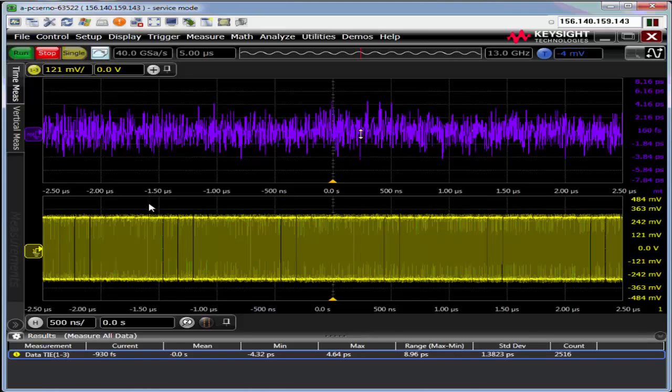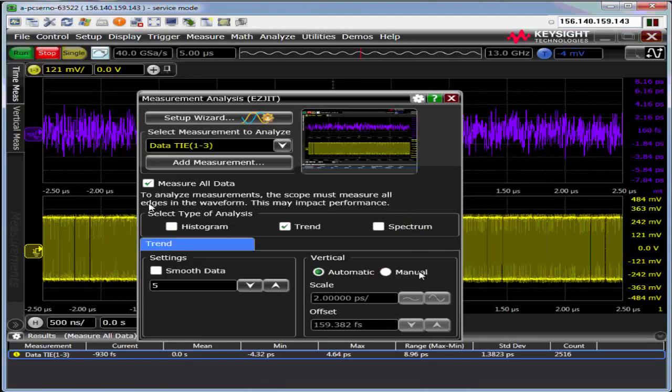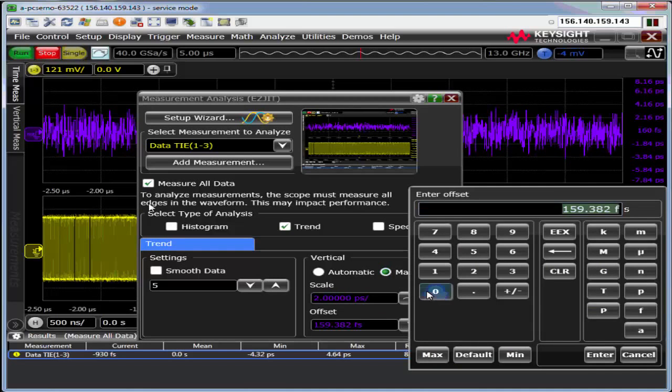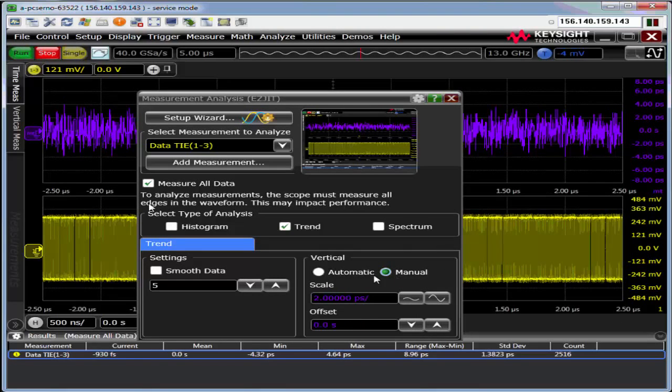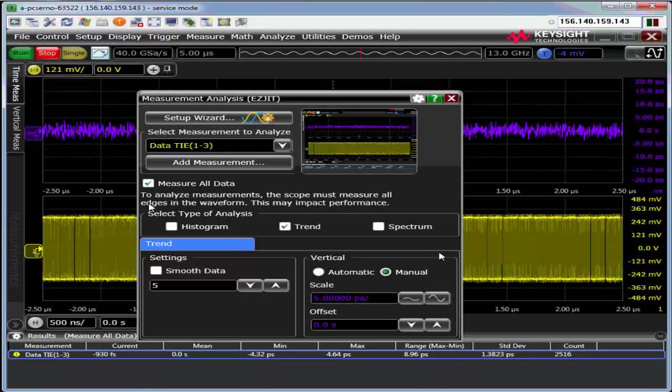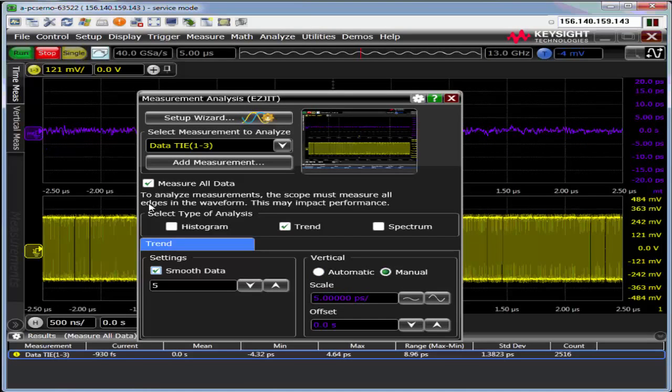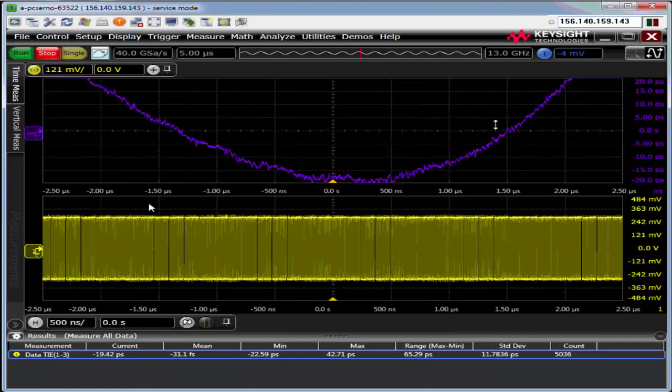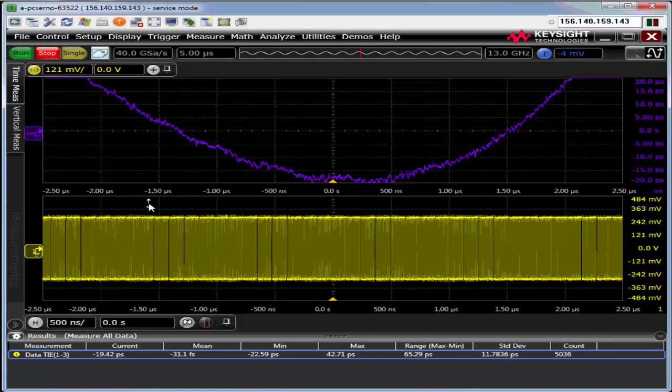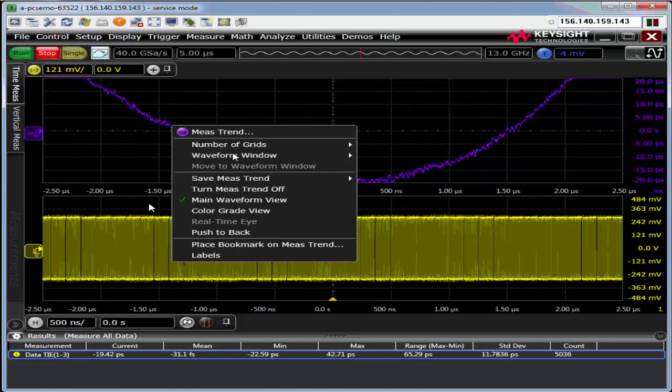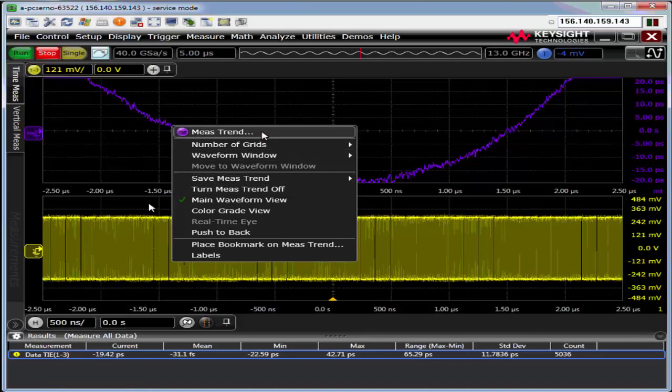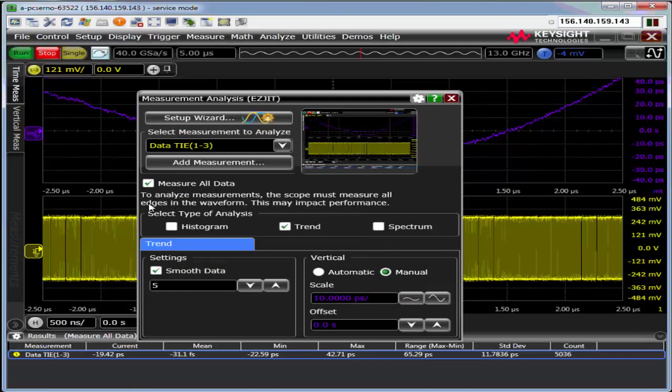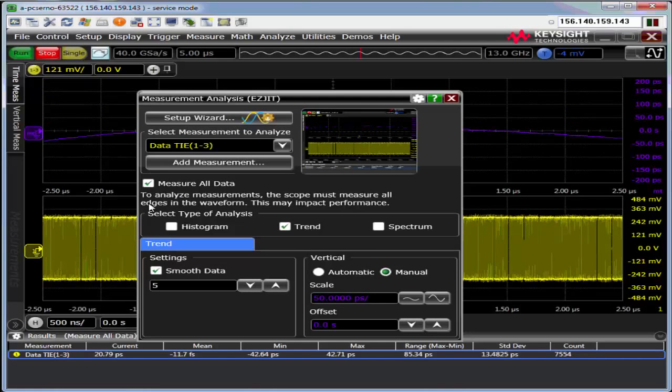You can also right-click on it and I like to set the offset to zero picoseconds, zero time. We can control the scale here as well. I can turn on smoothing. Sometimes this is very helpful if you have a known jitter source. So on that note, let's turn on some jitter. Let's take a fresh acquisition here. We can see that all of a sudden, instead of a flat line, I kind of have this shape. Maybe it looks like a half period maybe I have.